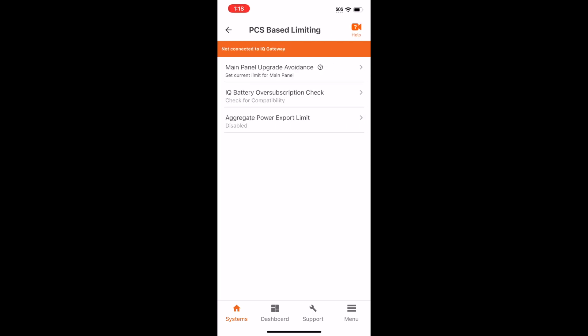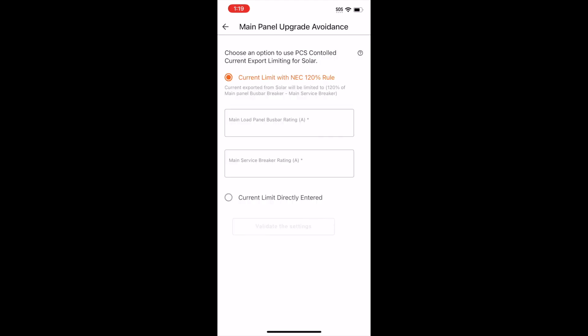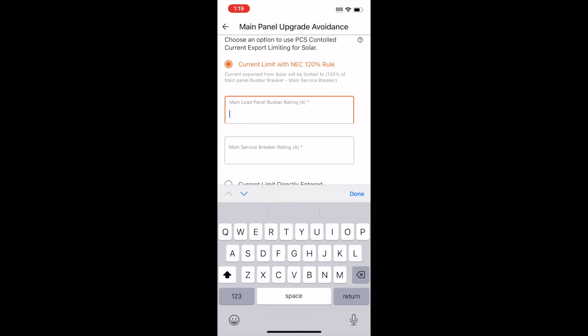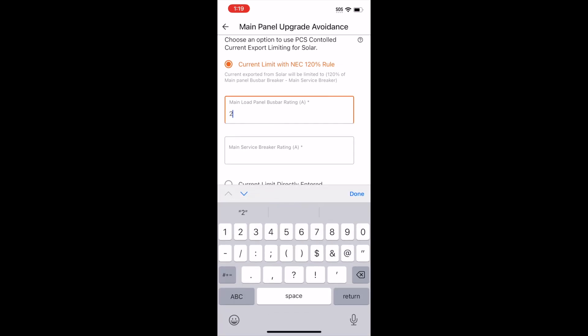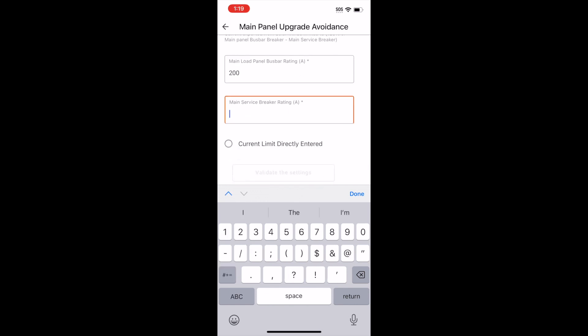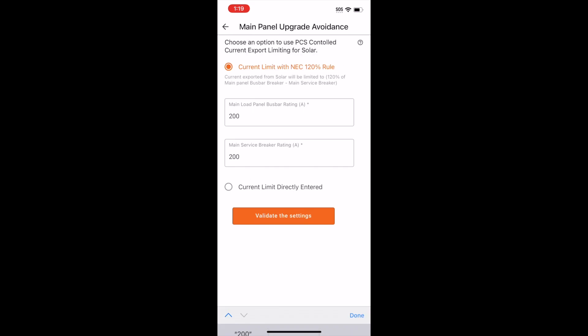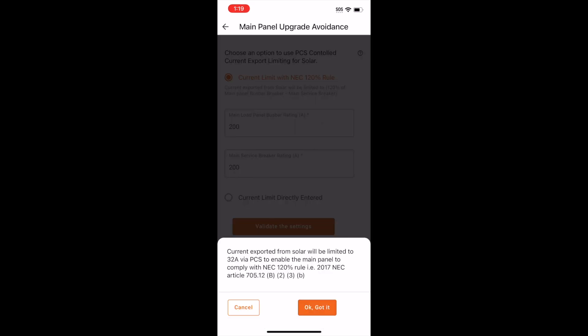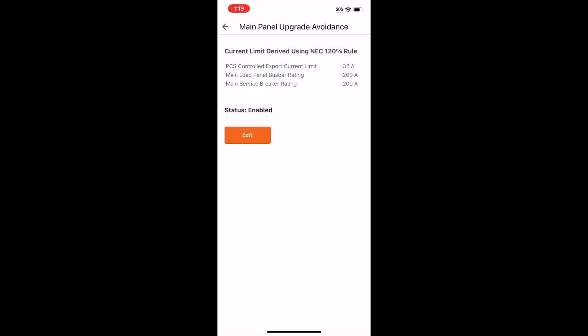Now refer to your site-specific design and select one of the two options. The app has a helpful tool that does a quick calculation based on the 120% rule. You enter the Service Panel Bus Rating, then the Main Breaker Rating, and the app suggests the likely calculated current limit.